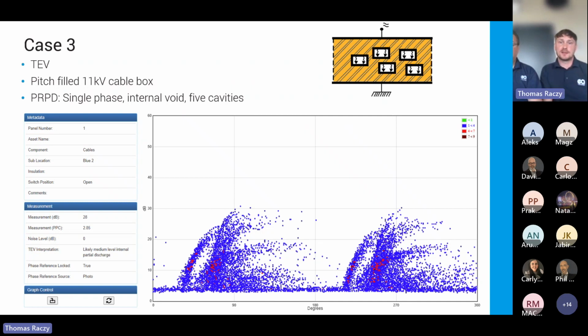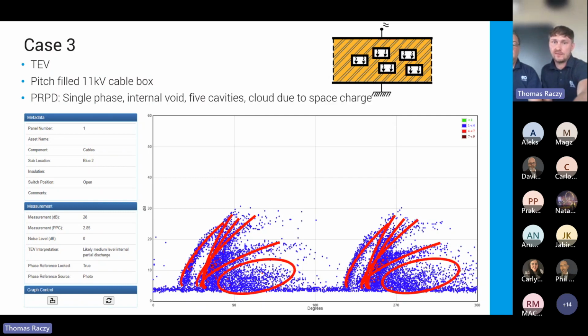Another case study, it's a very interesting one. So single phase discharges, very well-defined clustering events 180 degrees apart, but looking at the actual phase resolved pattern, you can probably appreciate there are multiple sites of discharges, because we have multiple leading edges. That'll be the first group of those leading edges, second one, third one, fourth one, and finally the fifth one. So very typical for hard insulation, epoxy resin type or pitch-filled insulation, those wave fronts. And what we also have is that loose clustering of the events after the initial discharge on each of those cavities.